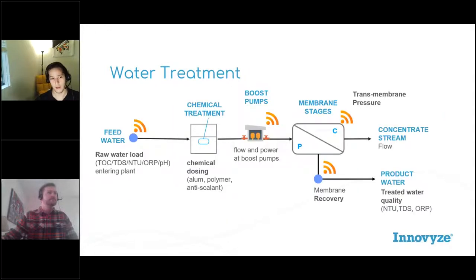In water treatment, we use all the sensors associated with incoming flow, incoming influent water quality, and effluent water quality, and we can start optimizing the chemical dosing required for the flocculation process or the membrane production process, decreasing the amount of reject or increasing production through a membrane. Filter backwash schedules can also be optimized to use less energy or prevent duplication of activities when you have multiple trains. And of course, all the energy and pumping required within a plant can be looked at too.